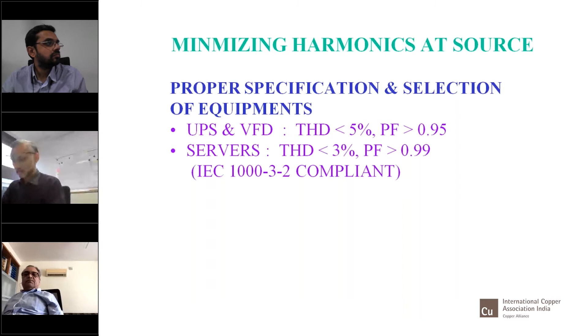Then we have servers. Earlier the servers used to be very bad in harmonics, but fortunately for the last 7-8 years even these are not bad. When you buy new servers, they give less than 3% harmonics and 0.99 power factor, so there is no problem. And of course all servers are always protected by UPS, and I'll show you later in the slide that UPS is a firewall for harmonics. All servers are IEC 1000 compliant.